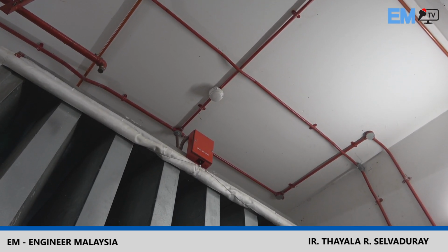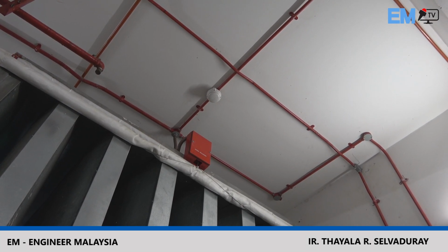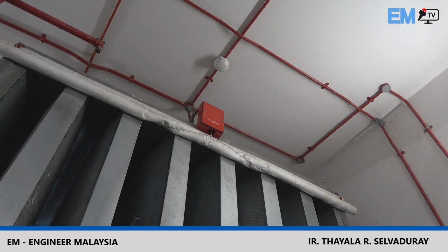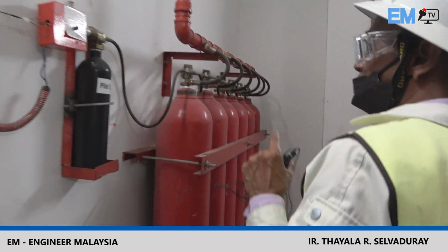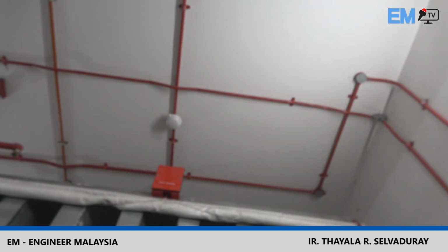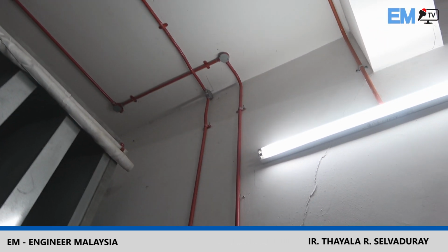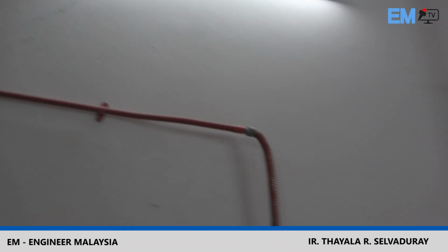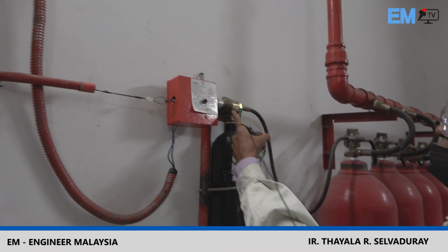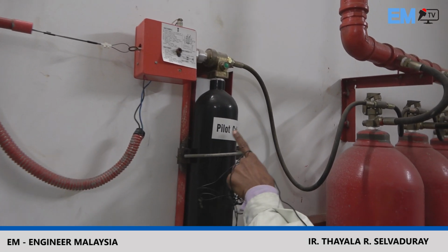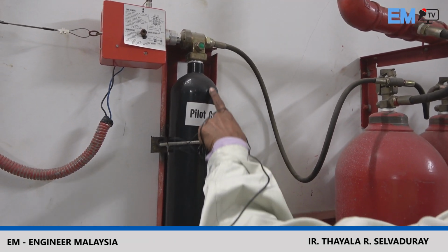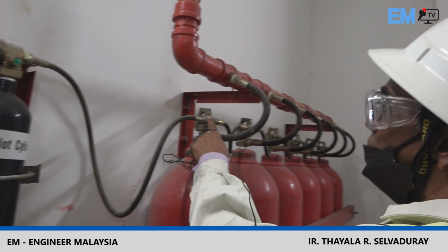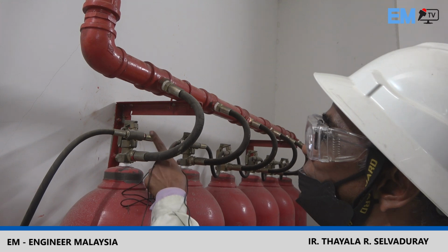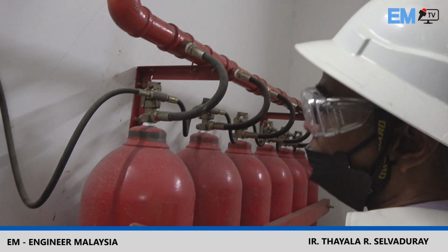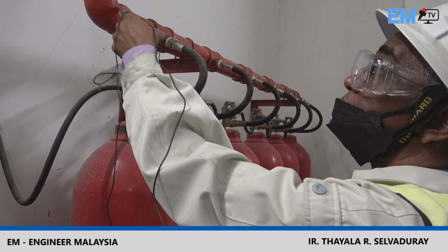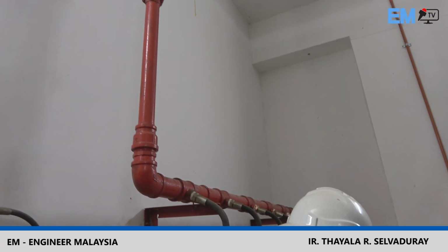When the alarm rings, it's telling you that it's going to activate the CO2 bottles. When the CO2 bottles activate, no one should be in the room. These are the CO2 bottles. What happens is the signal comes from the alarm panel, electrical supply comes to the alarm panel through this wire here, and energizes the solenoid here. Once the solenoid is energized, there's nitrogen gas here. The nitrogen gas is pumped into here, activated here, and this lever is opened. Once this lever is opened, carbon dioxide from these red color cylinders is released into the main line and goes up and sprays the room with carbon dioxide.